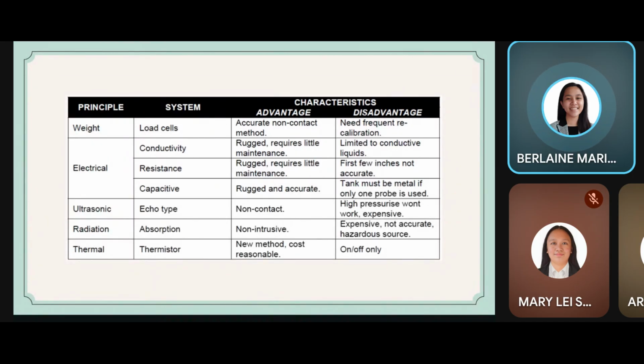And last po is yung radiation method. Hindi pala. Absorption is non-intrusive, meaning the measuring device does not touch the liquid, so it is useful in harsh or hazardous environments. The disadvantage is that it is expensive, less accurate compared to other methods, and hazardous because it uses radiation, requiring strict safety measures. And lastly po is yung thermistor method, which is new and has a reasonable cost, which makes it more accessible. A thermistor is a temperature sensor that detects changes when it is covered by liquid. Its disadvantage is that it only gives on or off readings, meaning it cannot provide continuous level measurement.